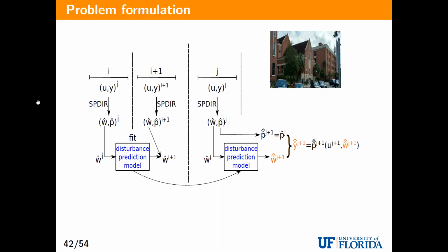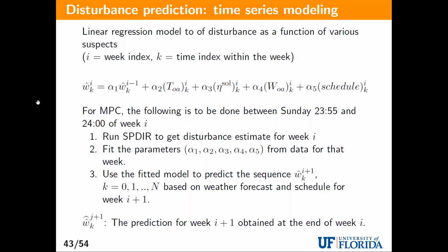By fitting this model, I mean I have estimated these parameters alpha 1, alpha 2, alpha 3, all of that. And then I use the weather forecast and a schedule forecast to predict what the disturbance is likely to be next week or next day. Okay.